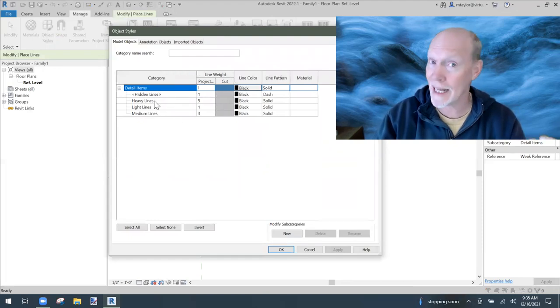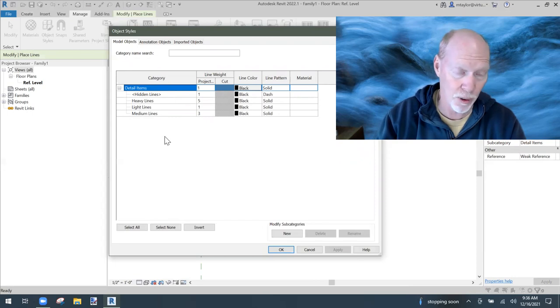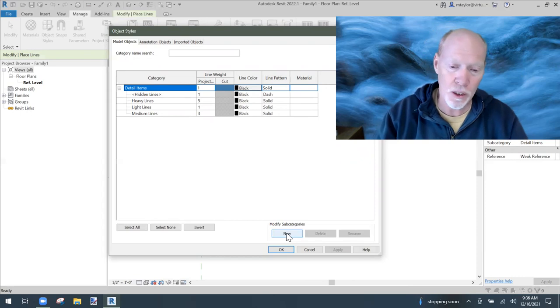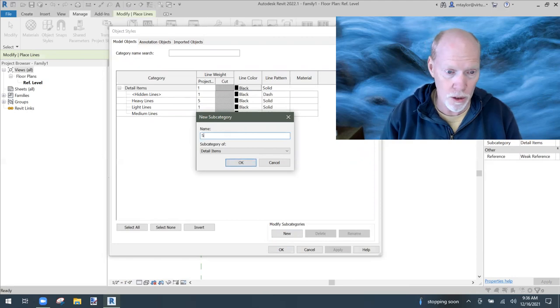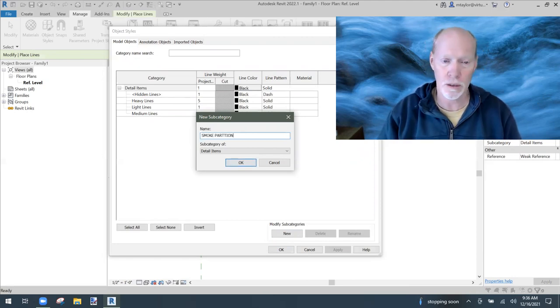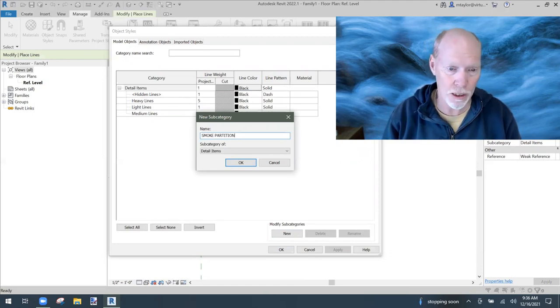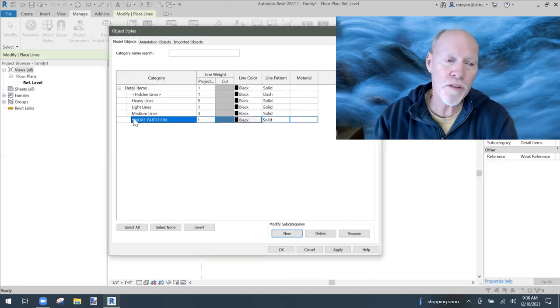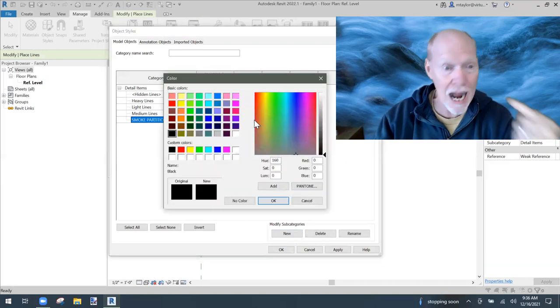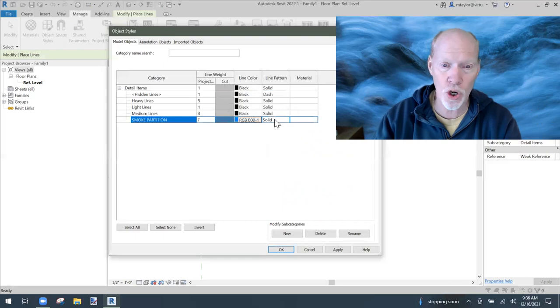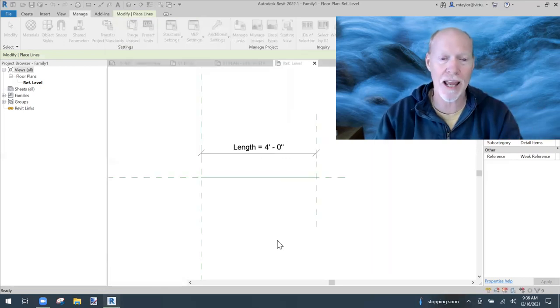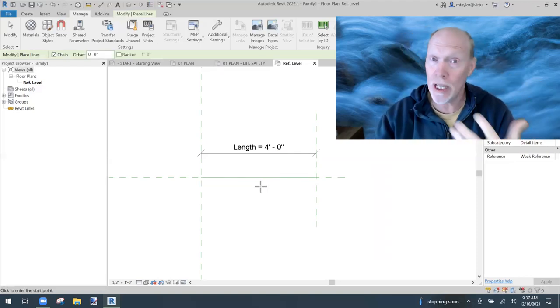I need a subcategory called Smoke Partition. Click New at the bottom and type 'Smoke Partition.' I want it to be a wide line — I'll give it a line weight of 7. I don't want it to be black, so I'll pick blue for the color. And I don't want a solid line pattern — I want it to be a dotted line. Click OK.